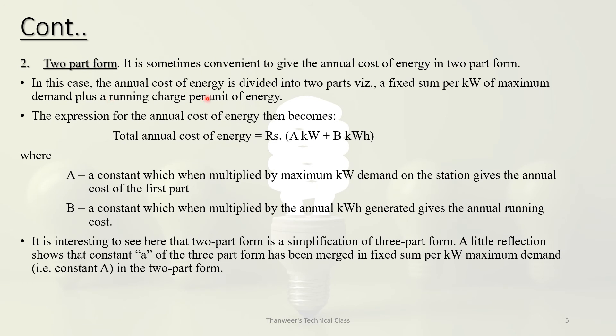It is sometimes convenient to express the annual cost of energy in two-part form. In this case, the annual cost of energy is divided into two parts: a fixed sum per kW of maximum demand, plus a running charge per unit. The expression is: Total cost = A × kW + B × kWh, where 'A' is the constant which when multiplied by maximum kW demand gives the annual cost of the first part, and 'B' is the constant which when multiplied by annual kWh generated gives the annual running cost. The two-part form is a simplification of the three-part form.